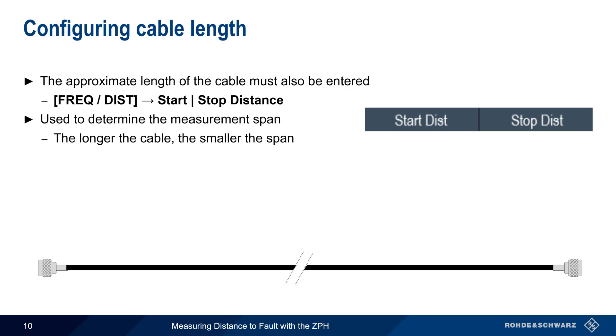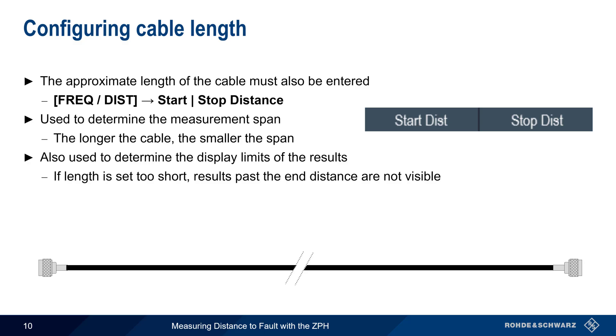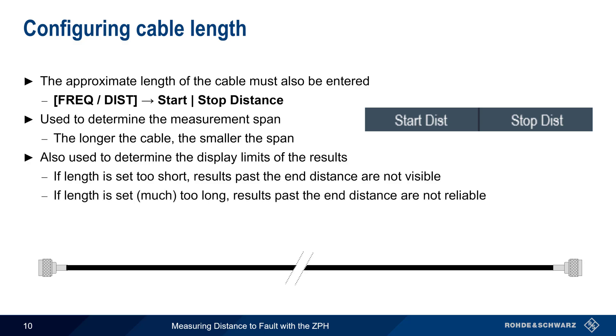The other reason why cable length must be entered is that it's used to determine the display limits on the results. If the length is set too short, then we won't be able to see any cable faults beyond this distance. Setting the length too long is also undesirable, since any results past the end distance will not be reliable. In most distance to fault measurement applications, the approximate cable length is known, but if the length has to be estimated, it's usually best to err on the side of overestimating the cable length.